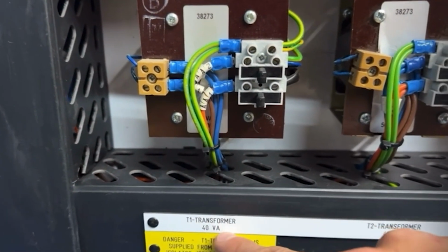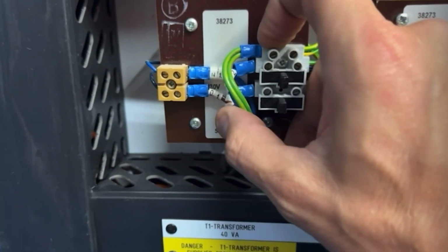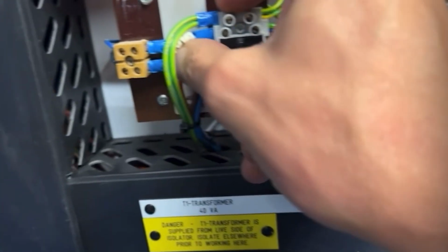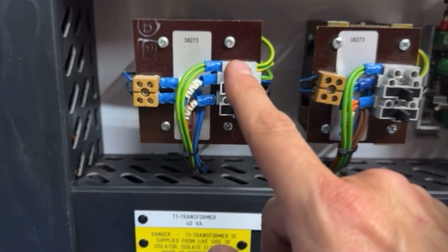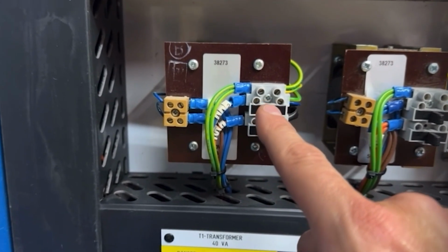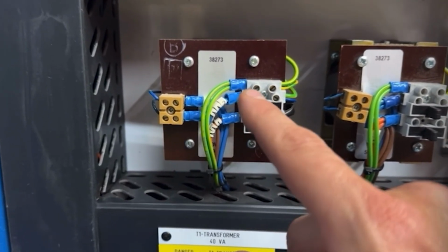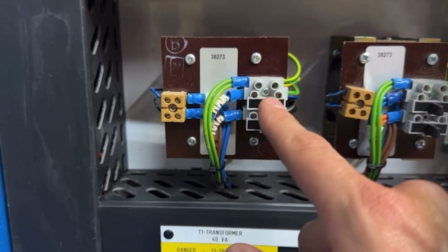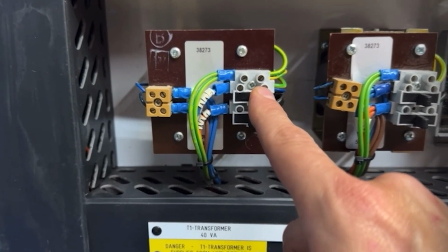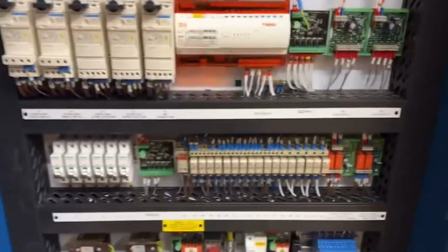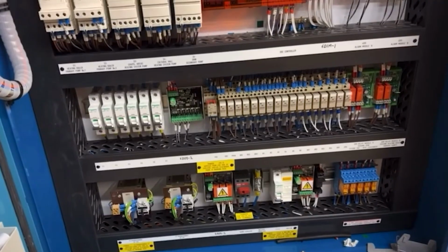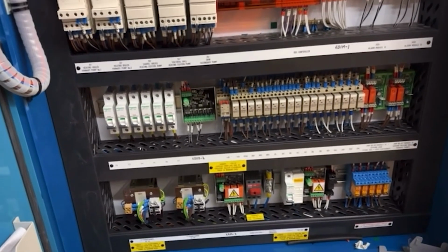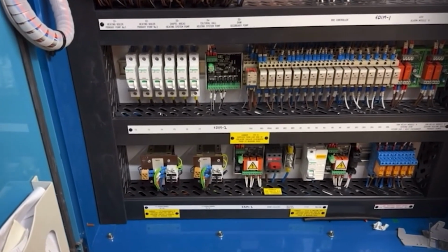I'm not taking this apart, like I say, but this transformer, T1, is a 40 VA transformer - 230 volt in, and it's 24 volt out. Remember, it's a transformer, not a power supply, so that 24 volt out is AC. That's very important to remember, because I suspect all the relays are AC, since I can't see a DC power supply in here.